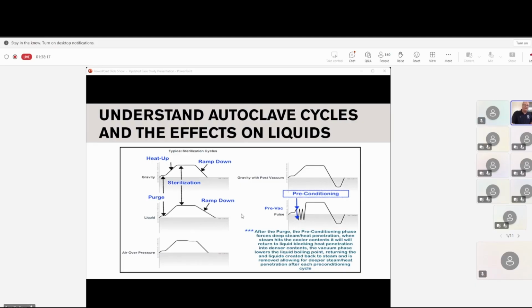So when you get right above sterilization, it's going to go through a very quick check. It's going to check to make sure, especially in the new ones, that the probes all meet, your chamber probe, your drain probe. Then it's going to check your steam pressure to make sure that your jacket pressure, your everything meets, because pressure and temperature correlate evenly. So at 15 psi, that should equate to 121.